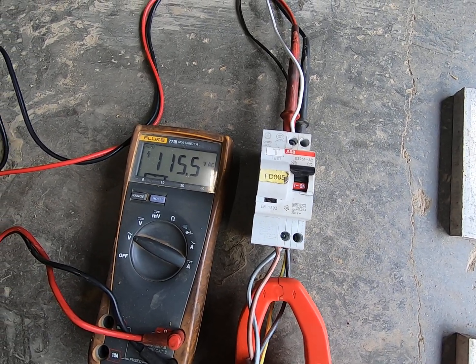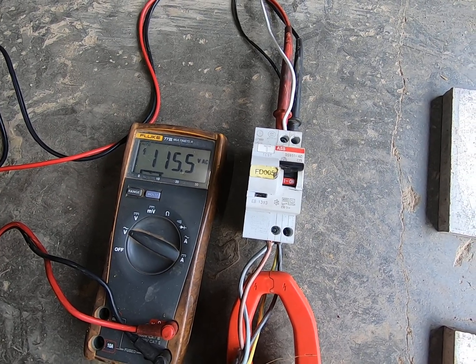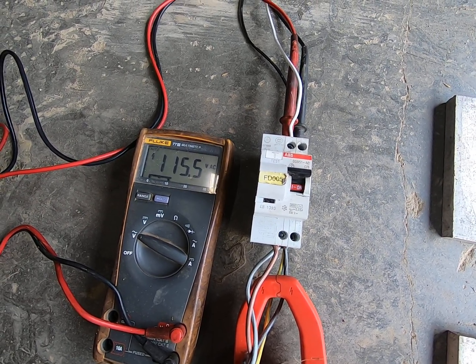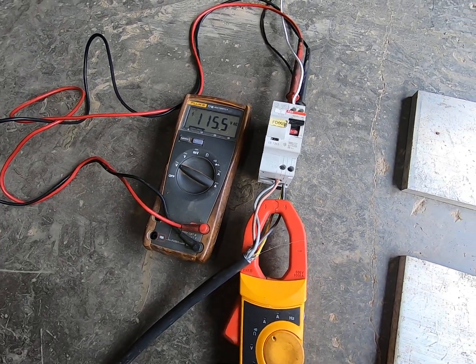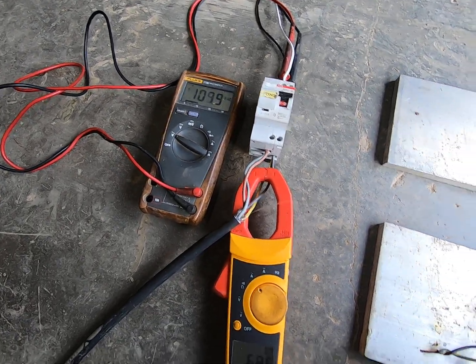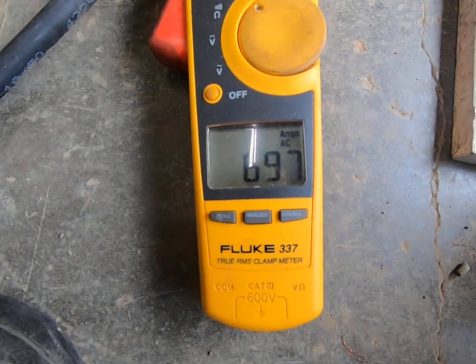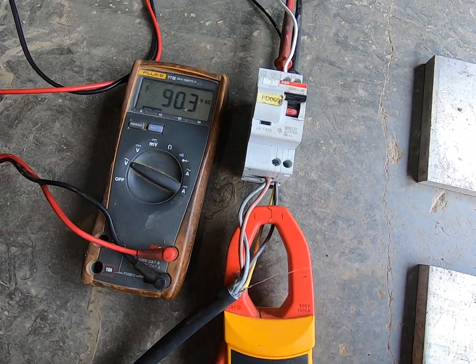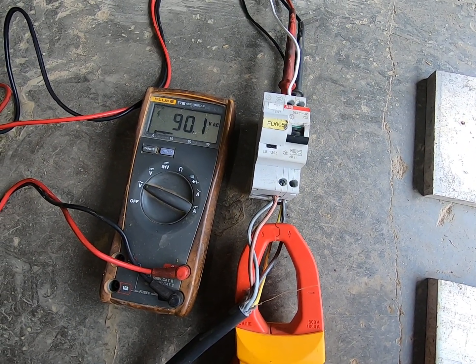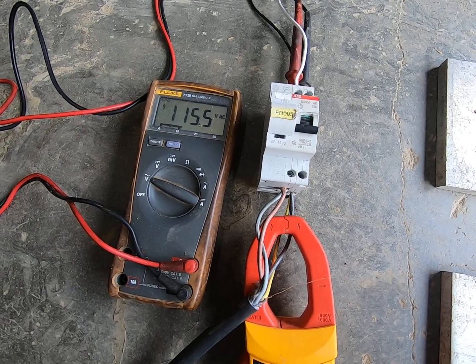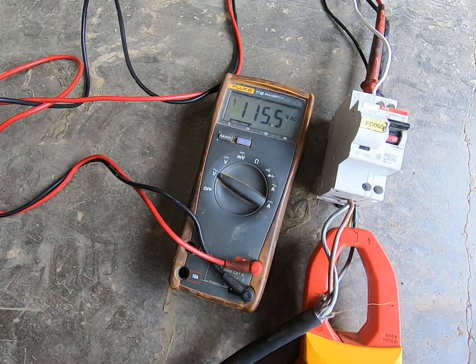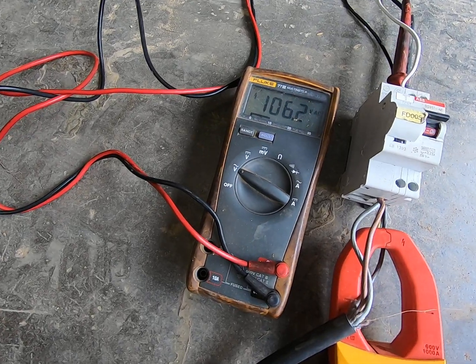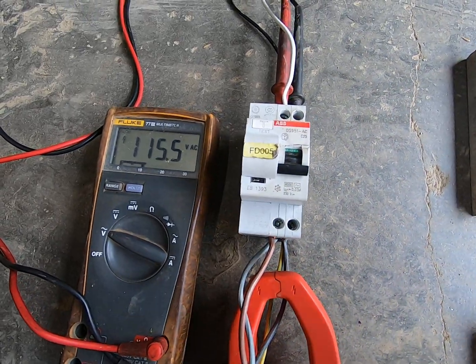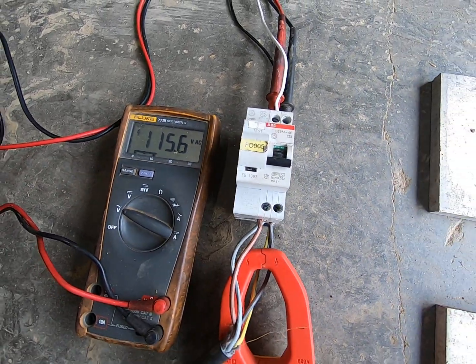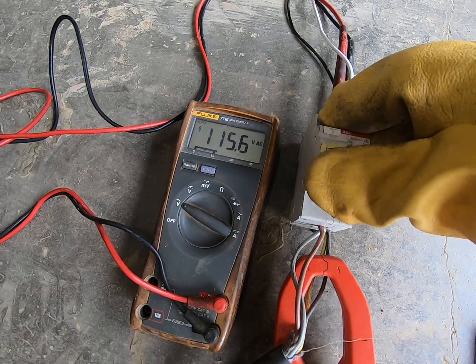So again, 5 to 10 times for instantaneous. It's a 25 amp breaker, so anywhere from 125 to 250 amps, it would trip immediately, but we're not seeing that. So again, we're shorted, we have 70 amps. Probably takes a good 5 seconds or so for the breaker to trip. You can also see during that test my voltage drops down to about 90 volts. Obviously, the more often I do this, the breaker gets hot and it's going to trip sooner.